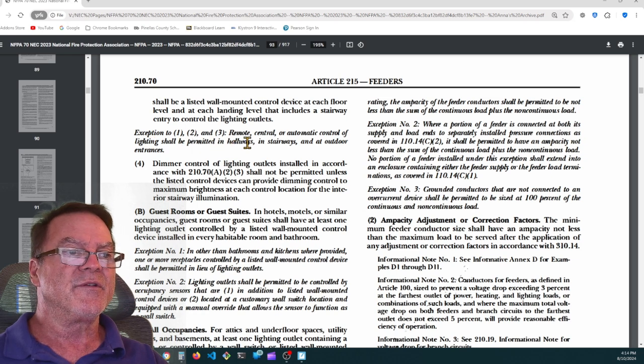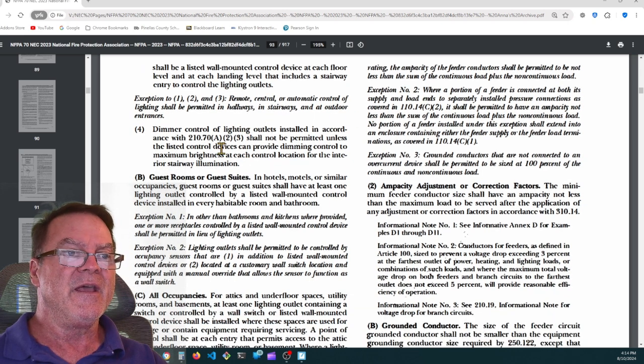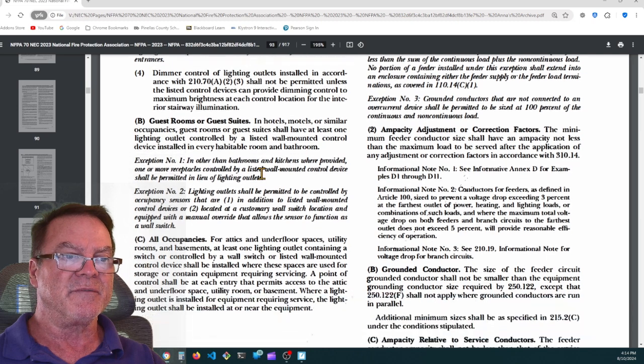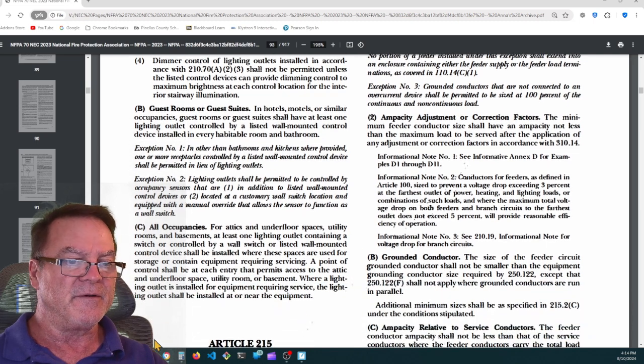Exception to 1, 2, and 3, remote, central, or automatic control of lighting shall be permitted in hallways, stairways, and in outdoor entrances. Dimmer control of lighting outlets installed in accordance with 210.70(A)(2)(5) shall not be permitted unless the listed control device can provide dimming control to maximum brightness at each control location for the interior stairway illumination. All right, very good.